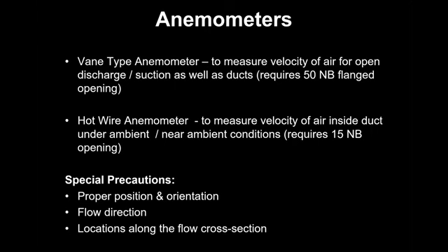Now the special precautions are simple, more or less on similar lines. The position and orientation should be correct. Flow direction is important, because with anemometers many times we feel that it doesn't matter, like anyway there are blades rotating, or there is a hot wire anemometer, how does it matter? Well, it matters. On the anemometer, they will specify the direction of flow. That needs to be followed. Second, the cross section: it should not be tilted or inclined, because that again is going to give you a wrong reading. So while inserting, it has to be exactly at 90 degrees to the flow of the air.